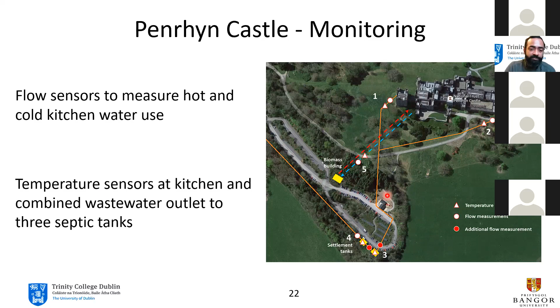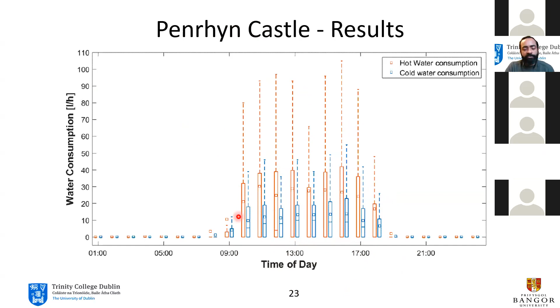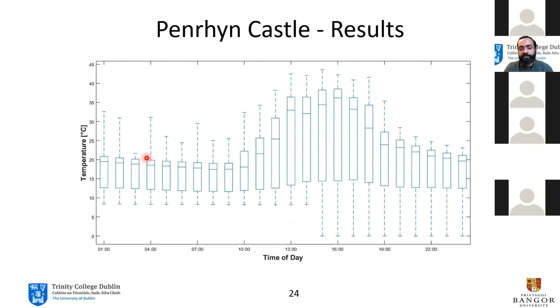The kitchen temperature was kind of as expected. They used hot water quite a bit throughout the day, up to 100 liters at times, but usually 50 to 60 liters, predominantly around lunchtime when the site was busiest - they didn't do dinner, so it was closed then. In terms of the actual water temperature, it ranged up to a maximum of about 45 degrees, which is very good for heat recovery during busy times - not so great the rest of the time, but still probably doing something.